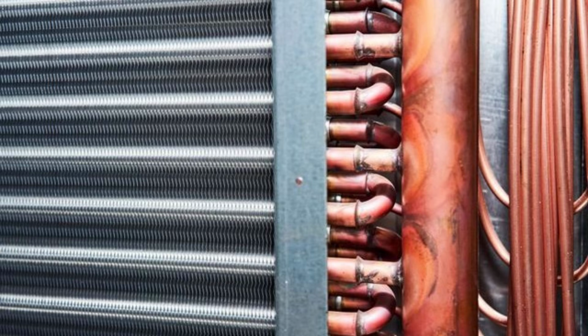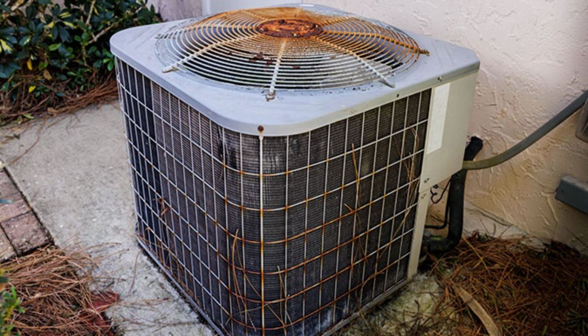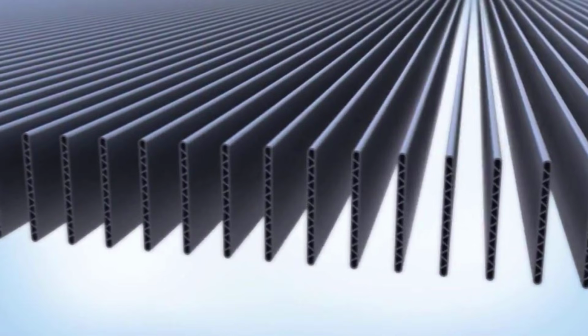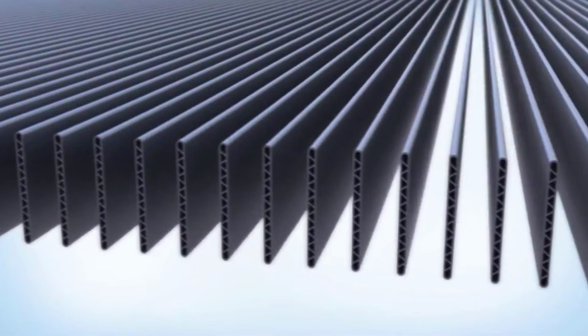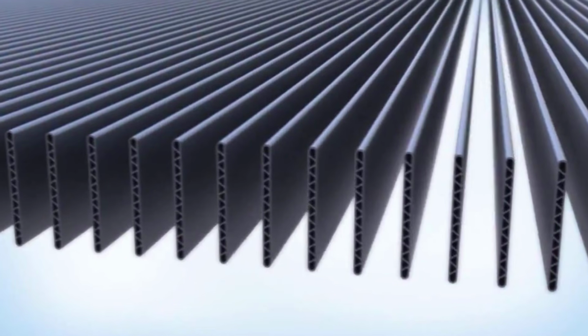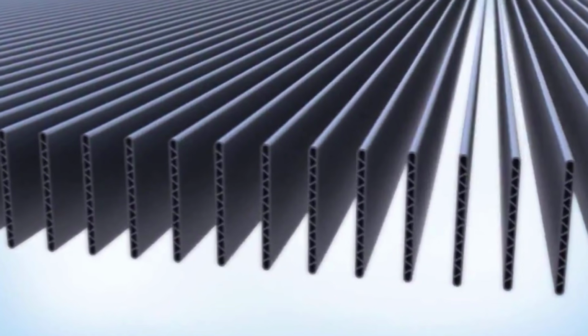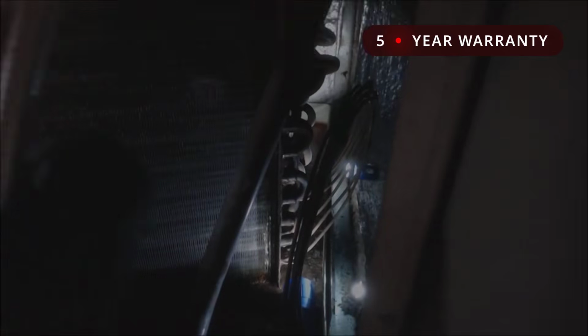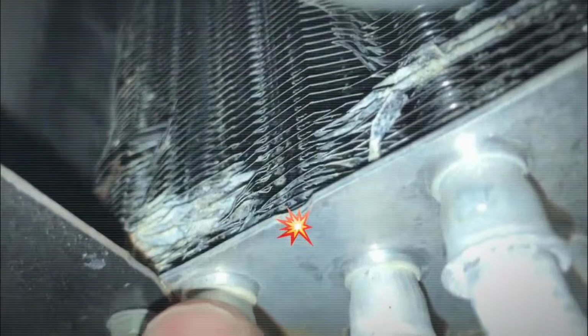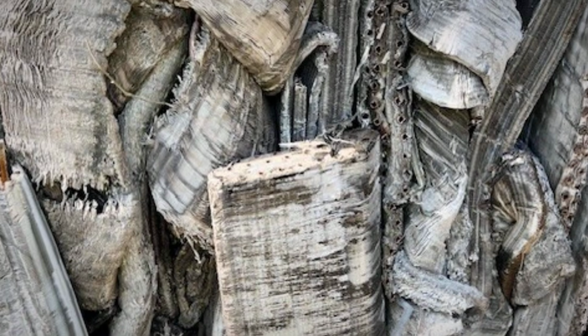They have replaced the thick, repairable copper coils that used to last 30 years with paper-thin, unrepairable aluminum micro-channel coils. These modern aluminum coils are highly prone to pitting, rotting out, and leaking expensive refrigerant gas right after the 5-year warranty expires. You cannot patch a micro-channel coil. When it leaks, the entire part is garbage.